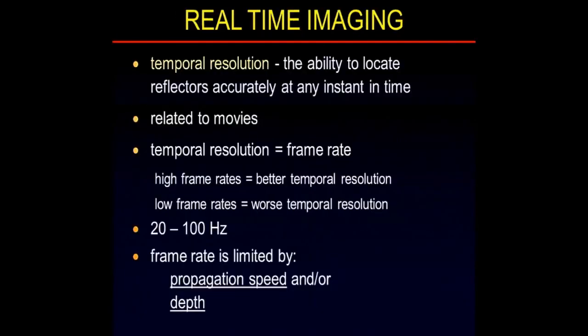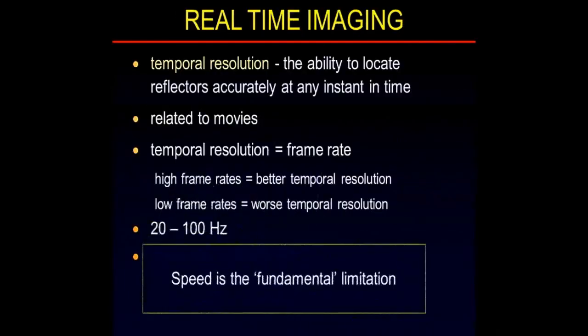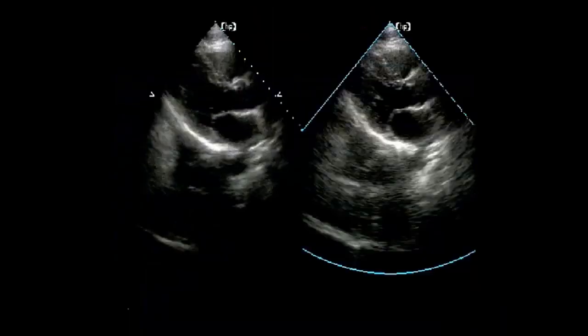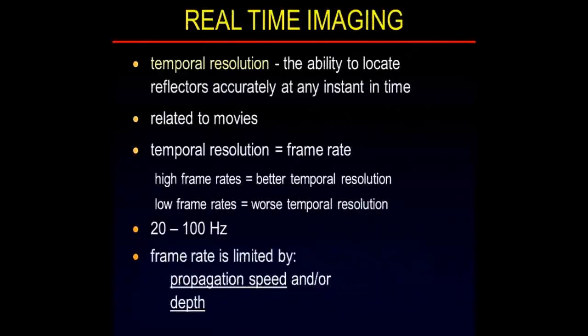But now, let's talk about temporal resolution. Temporal resolution asks the question, if something is moving, do I know where it is? And in order to know where it is at every instant in time, what do I need? A high frame rate. That's what I need, a high frame rate. Because if I have a low frame rate, I'm going to look like an old Charlie Chaplin movie. That herky-jerky thing. So temporal resolution is simply equal to the frame rate. The frame rate, on typical ultrasound machines, is between 20 and 100 hertz.